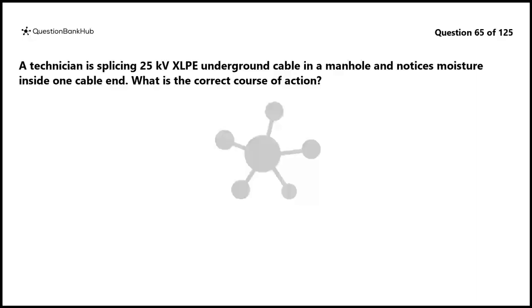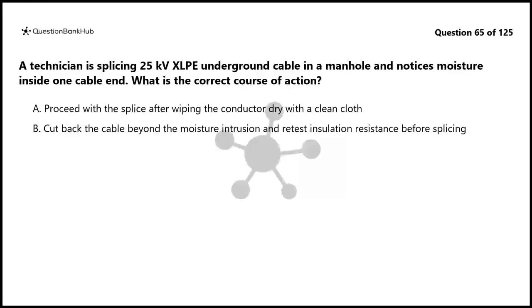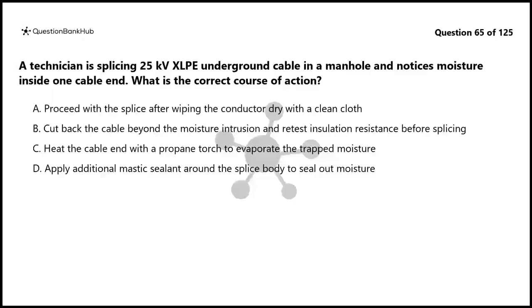Question 65. A technician is splicing 25 kV XLPE underground cable in a manhole and notices moisture inside one cable end. What is the correct course of action? A. Proceed with the splice after wiping the conductor dry with a clean cloth. B. Cut back the cable beyond the moisture intrusion and retest insulation resistance before splicing. C. Heat the cable end with a propane torch to evaporate the trapped moisture. D. Apply additional mastic sealant around the splice body to seal out moisture.